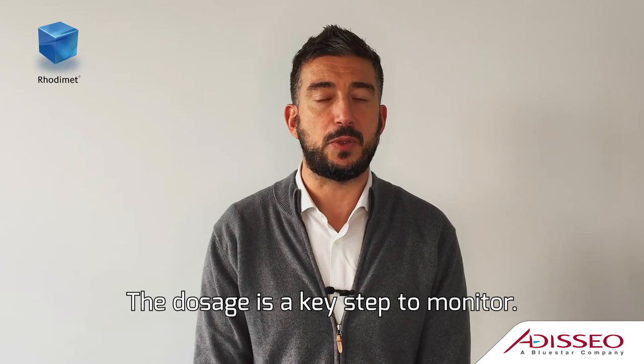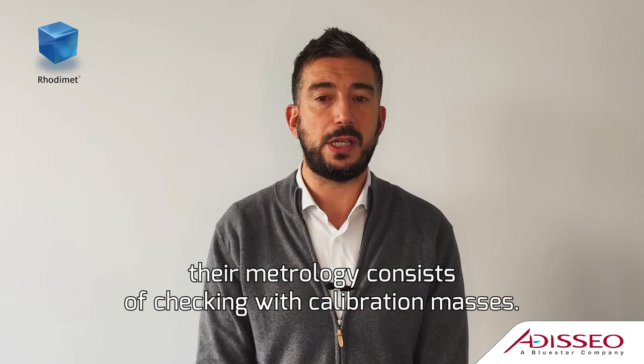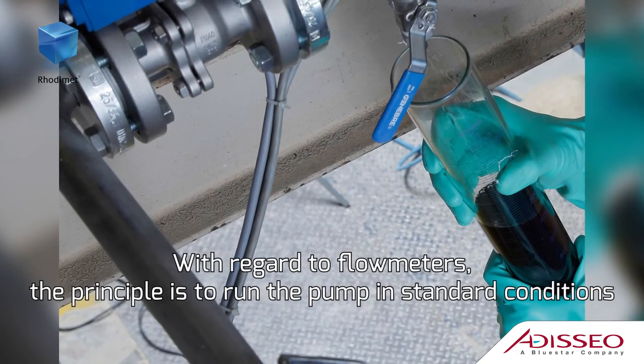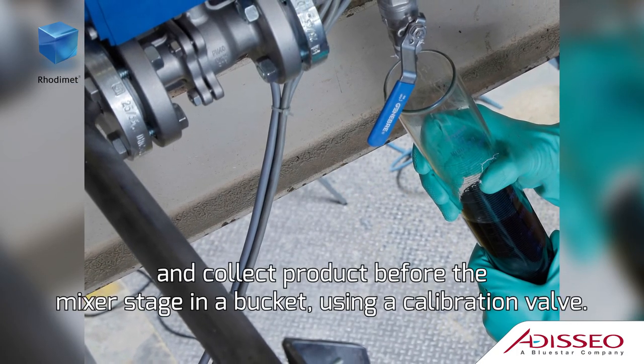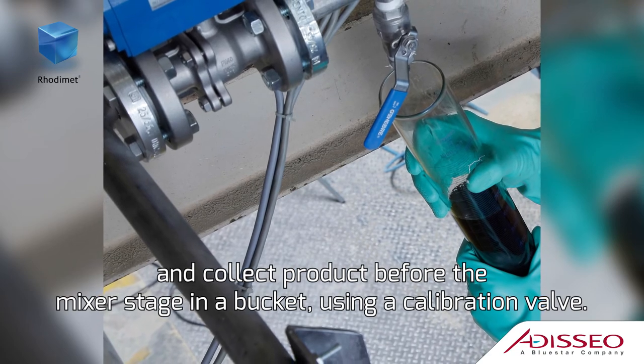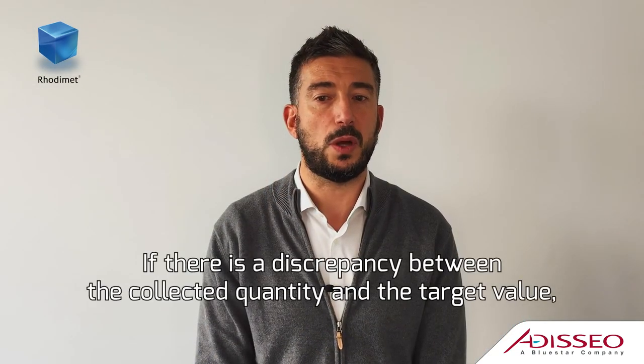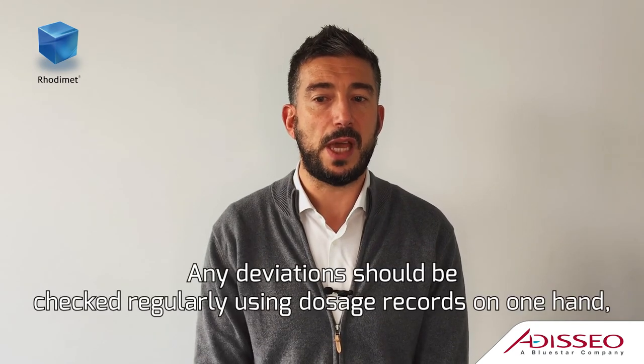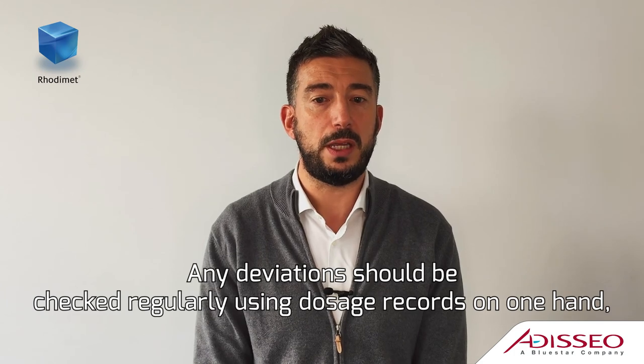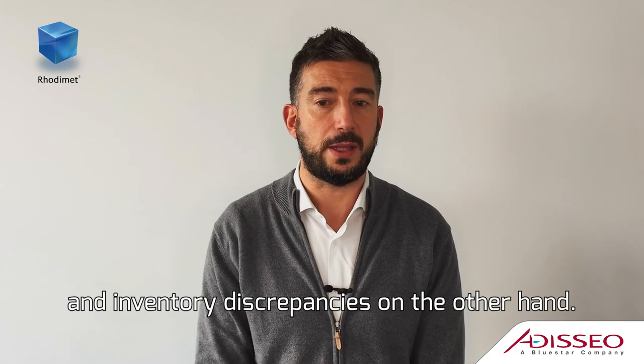The dosage is a key step to monitor. If the feed plant is using scales, their metrology consists of checking with calibration masses. With regard to flowmeters, the principle is to run the pump in standard conditions and collect product before the mixer stage in a bucket using a calibration valve. If there is a discrepancy between the collected quantity and the target value, some adjustments should be made. Any deviations should be checked regularly using dosage records on one hand and inventory discrepancies on the other hand.